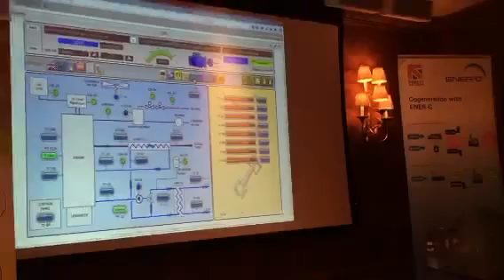This is the exhaust temperature schematic, and this is taking readings from each of the individual cylinders. The Ener-G 150 is an 8-cylinder V8 engine, so it has 8 exhaust outlets, and we have thermocouple probes which are fitted into each of these. This then gives us a temperature, and we can do the diagnostics from that point of view. If we've got a low exhaust temperature, we may have a spark plug failure. If we have a high exhaust temperature, it could be a low cylinder pressure. And there's various options on the bottom which John's been activating, which show averages and minimums, maximums. So it's a good diagnostic tool for the engineers.